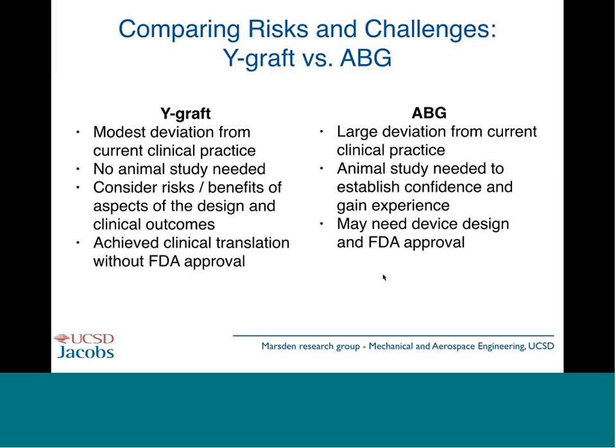Now with the ABG, it's a different story because the deviation from current clinical practice is viewed to be much larger and much higher risk from the point of view of the surgical community, especially because it involves surgery on neonates. And so here, this is a case where we really are going to need to do an animal study to gain confidence and gain experience on the part of the surgeons and evaluate the hemodynamics. We may also need to go through a device design FDA approval process, although it's not entirely clear yet. That depends on the design.